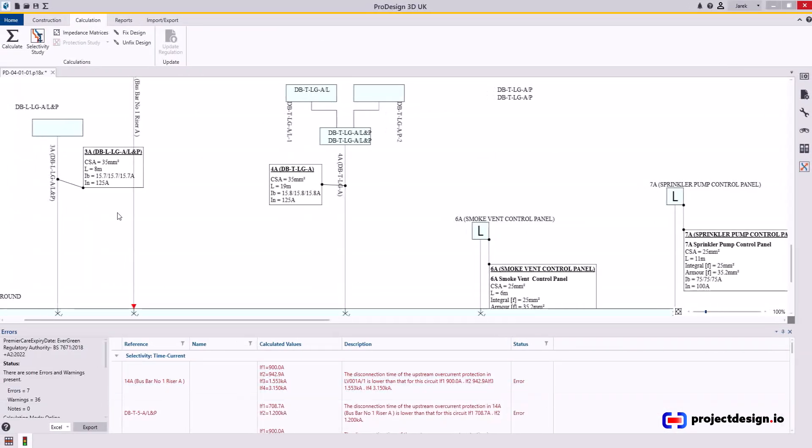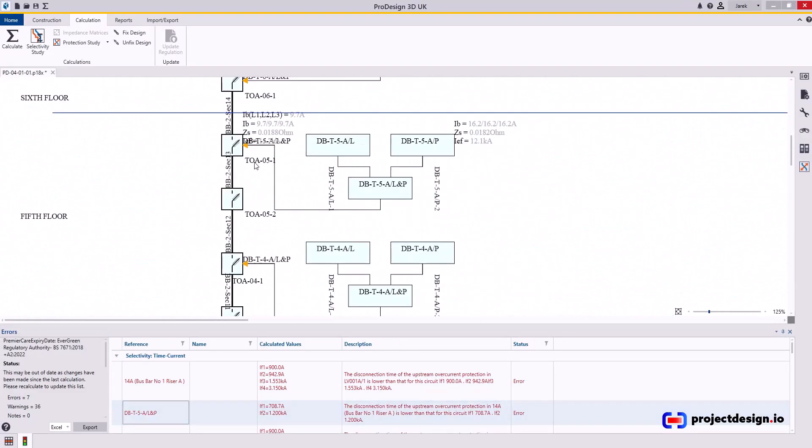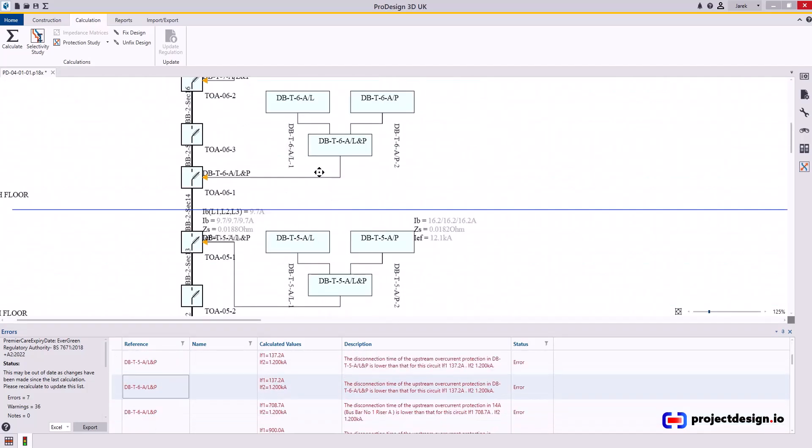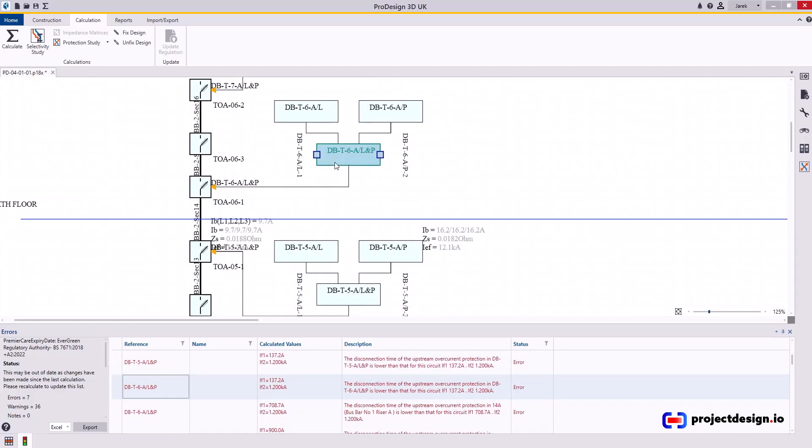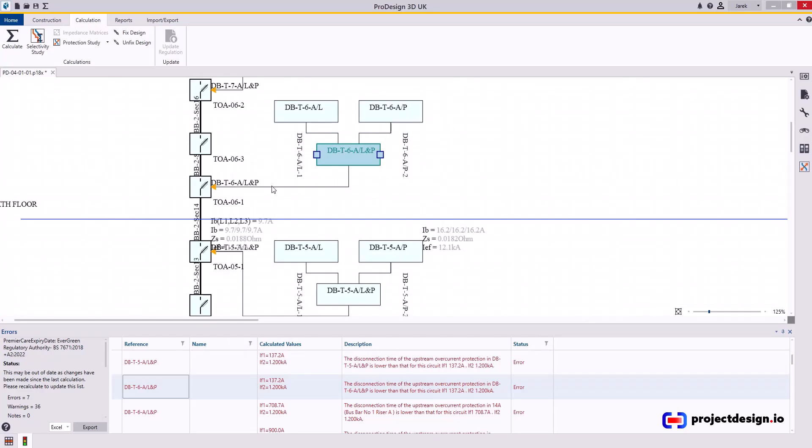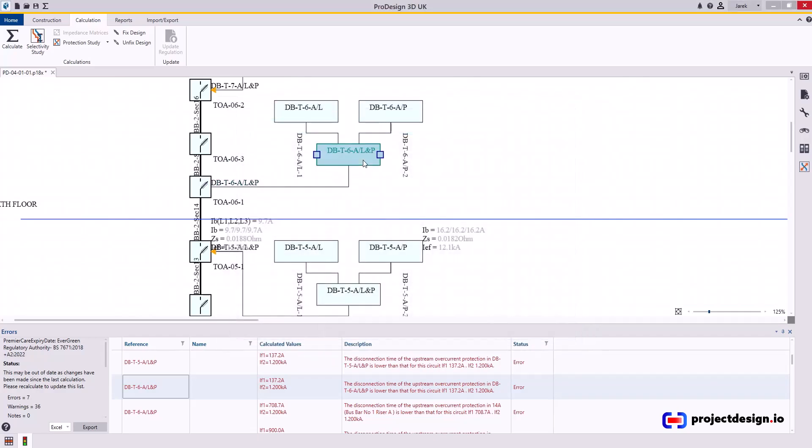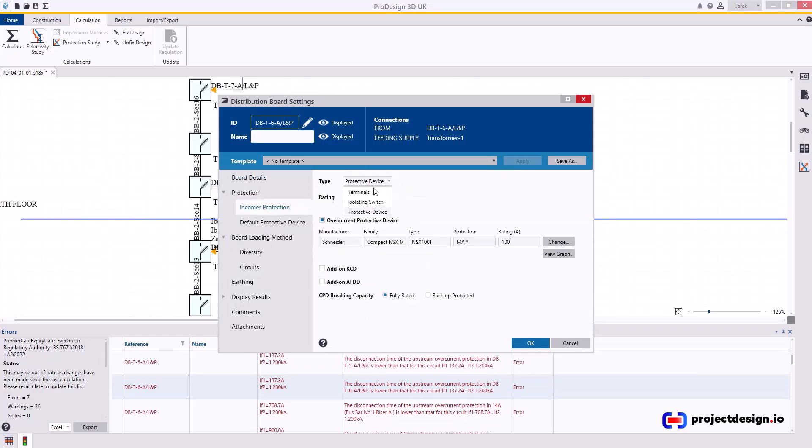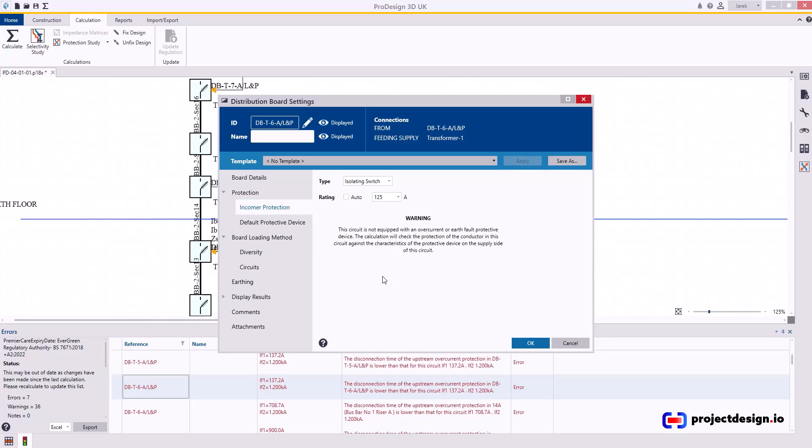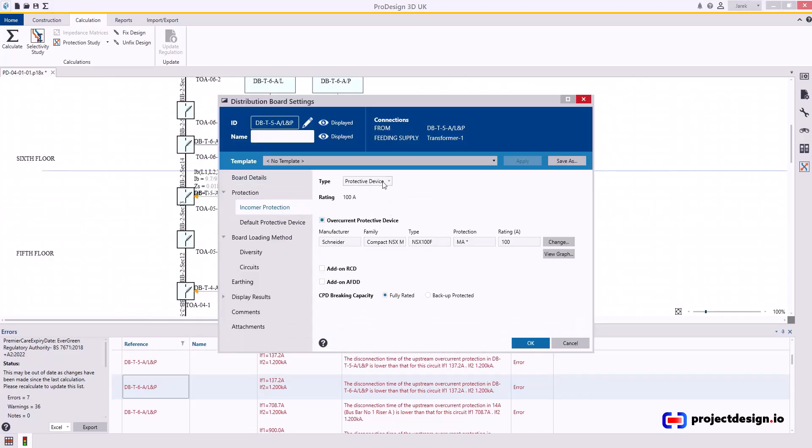Busbar number one, which is here. Let's see what the problem is. That's the problem. And the tap-off is a problem. I guess T5A, T6A, we may have a similar problem. This board incomer protection. It's not a protected device. It's not a 100-amp protected device. We've got 100 amp frame and 100 amp trip. And the cable also has protection, 160 amp frame and 125 amp protection. So what I'm going to do, I'm going to set this as an isolator because that's what it is in reality. Incomer protection, isolating switch, and I'll leave it as 125 amp. And in here, that's the same. Incomer protection switch, 125 amp. Let's run the calculations again.